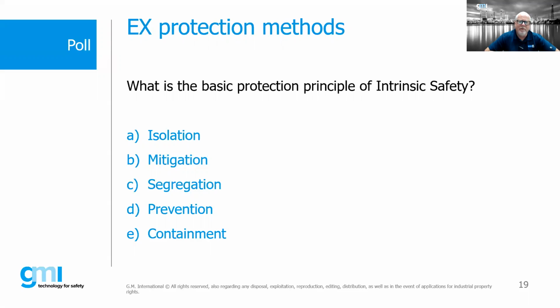That's correct, yeah - prevention. So what we're doing with intrinsic safety is we're in effect preventing an explosion from taking place, by making sure we're operating below the minimum ignition energy required to ignite the flammable gas-air mixture.